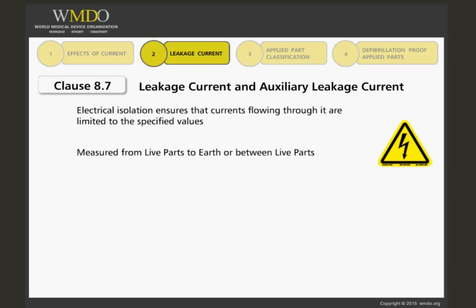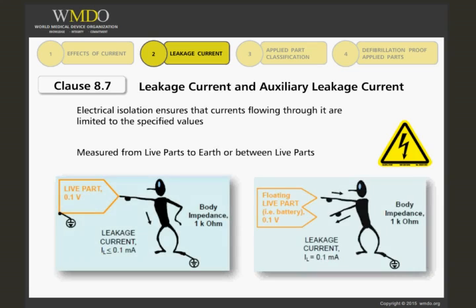These are measured from accessible parts to earth or between accessible parts. From the two drawings on this slide, you get two examples where 0.1 volts accessible, flowing through a 1 kilohm body impedance, yields 0.1 milliamps or 100 microamps.